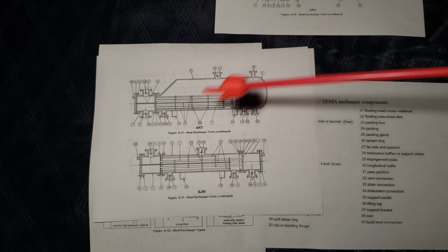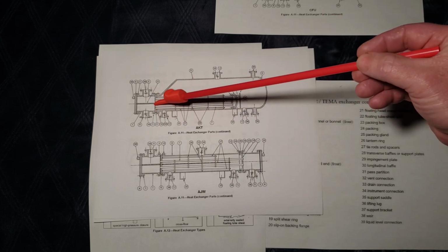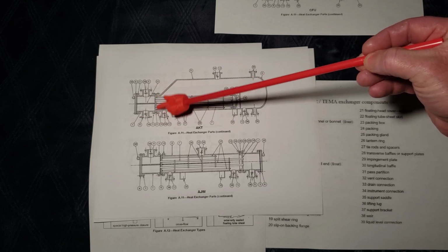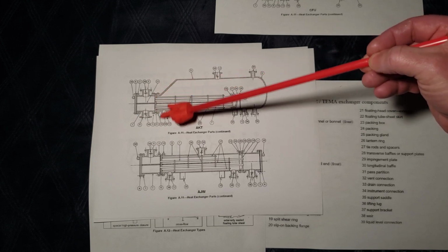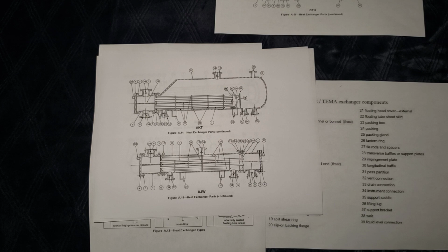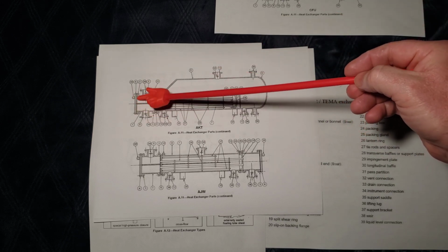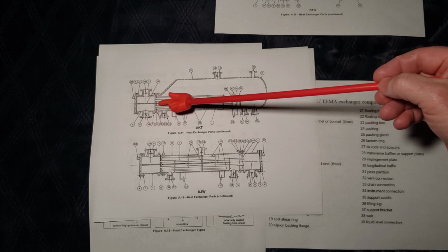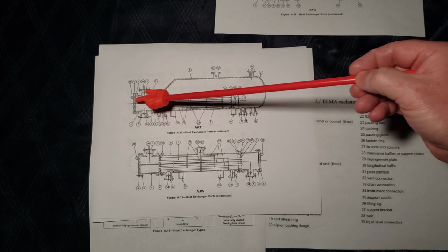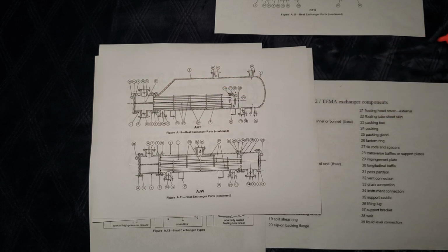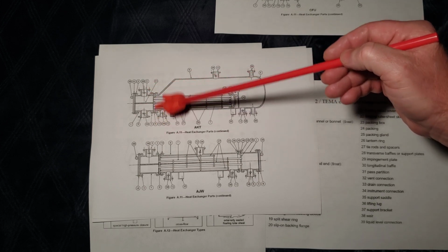That would be important. That way you could work on the tube face for whatever reason at the tube sheet without having to pull the entire gasket or try to roll the gasket onto the backside, which allows you to work on the tube sheet face without having to reach through the channel, which is why a lot of times they will thread the tube sheet.